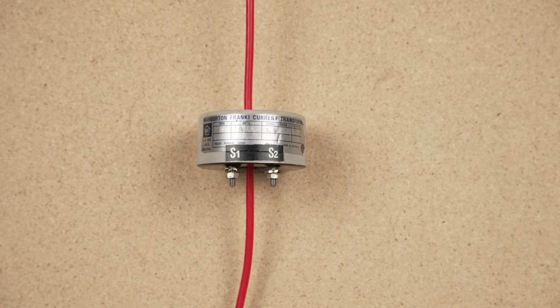There are no components in the CT secondary circuit other than the meter itself. Because an ammeter's impedance is very low, the connection produces a short circuit on the secondary winding. Whenever primary current is flowing, a proportional secondary current is also flowing through the meter circuit. The meter scale is calibrated to show the value of the primary current, not the actual secondary current in the meter circuit. The CT is designed to work constantly at full secondary current without damage.